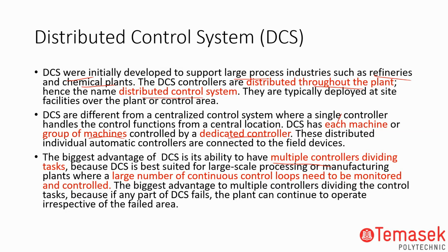It's a many to many relationship between the controllers and the devices. That's the key difference of this distributed system. With a normal PLC, it's one to many: one controller versus many devices, in terms of architecture and design.